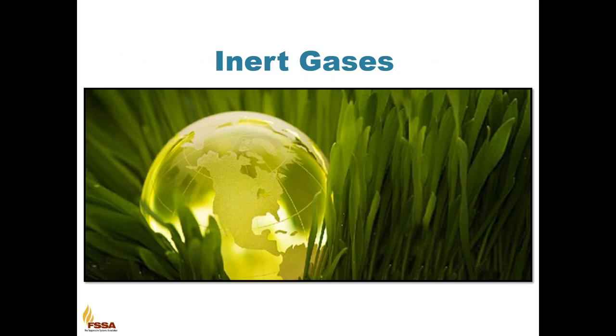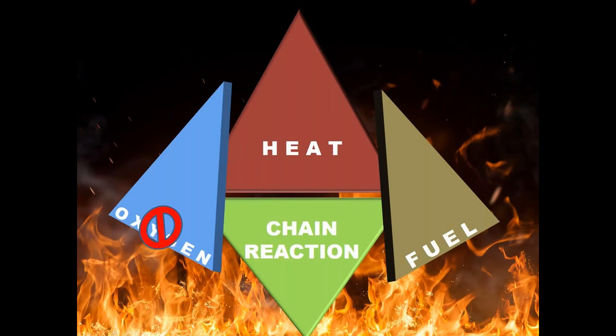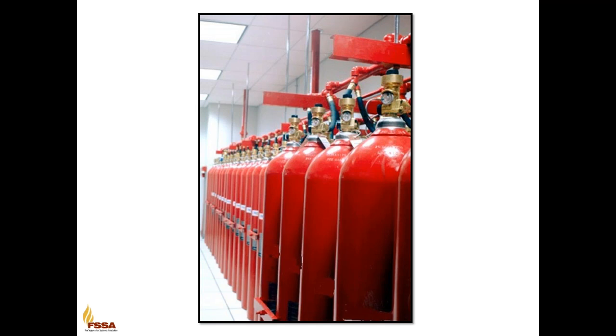The next group is the inert gases. Unlike the halocarbon agents, the inert gases suppress fire by means of oxygen displacement. They remain safe for use in occupied spaces due to the design of the systems. The inert gas discharged into a protected space reduces the oxygen level only to that which will prevent combustion, but not to an unsafe level for the occupants.